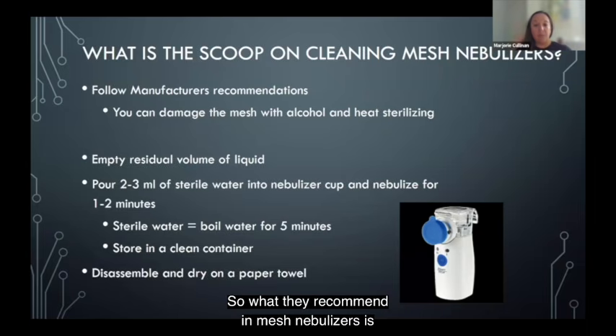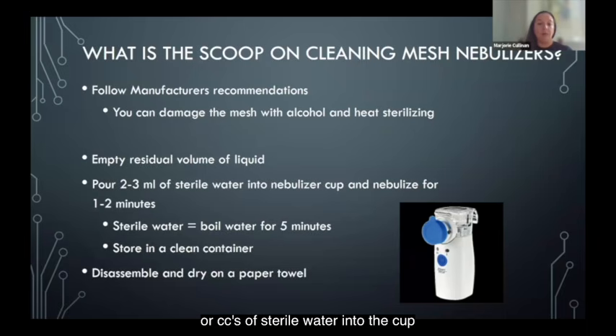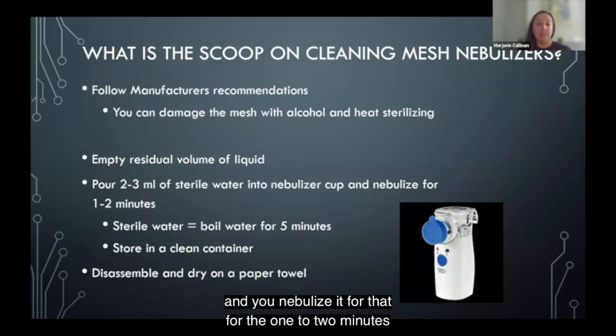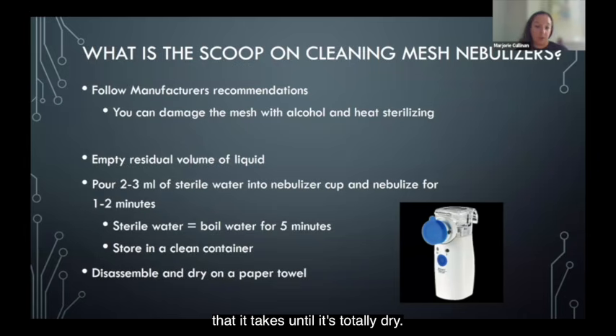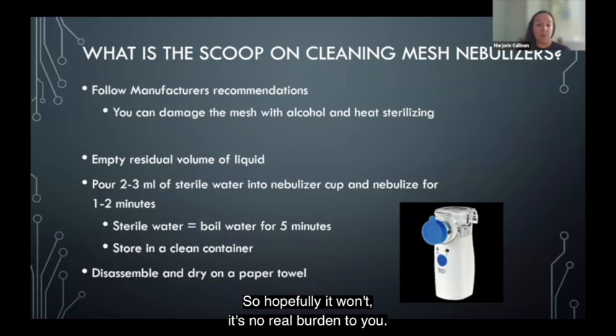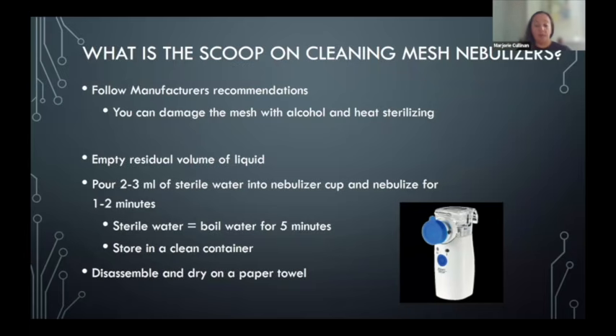So what they recommend in mesh nebulizers is that you empty any residual volume of liquid out of the nebulizer and you use 2 to 3 mLs or cc's of sterile water into the cup and you nebulize it for the 1 to 2 minutes that it takes until it's totally dry. Remember, sterile water is something you can make by just boiling it for 5 minutes, so hopefully it's no real burden to you. And then you want to store it in a clean and dry container, and also that paper towel technique so that it dries open.